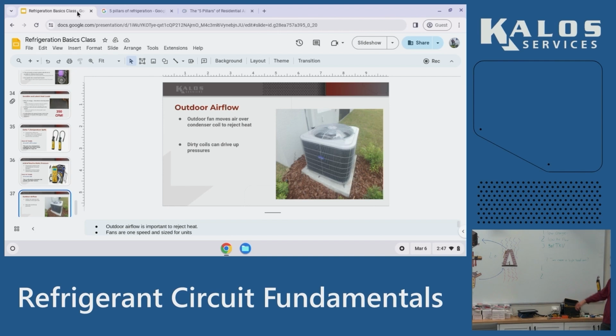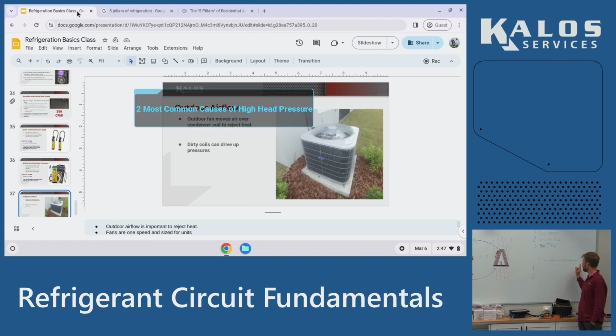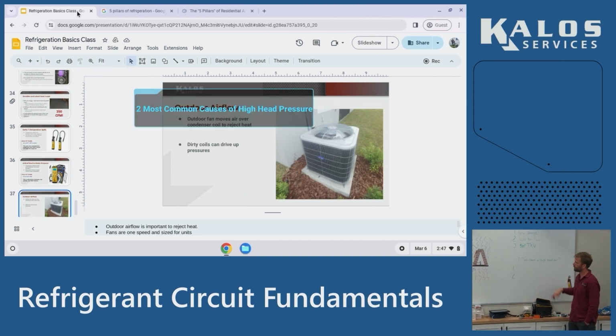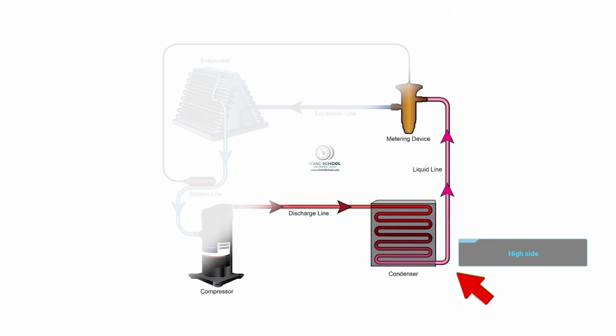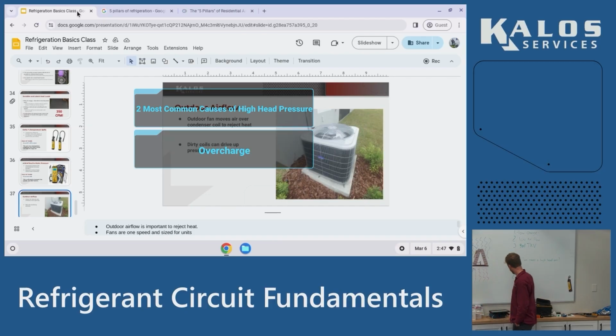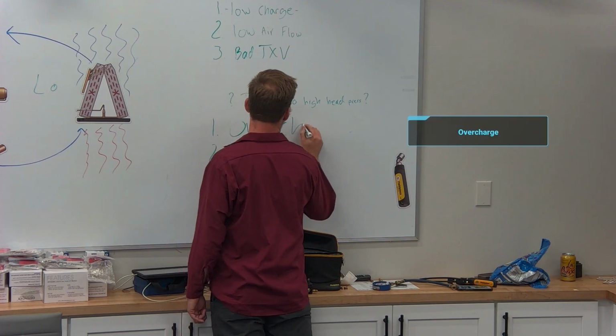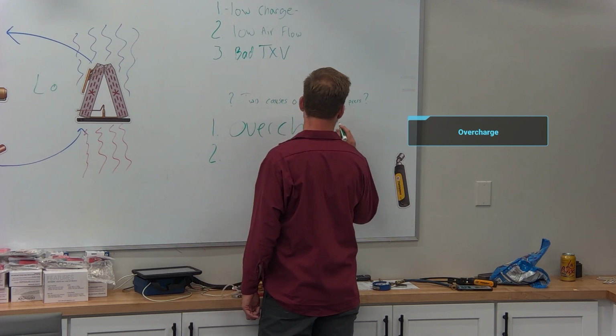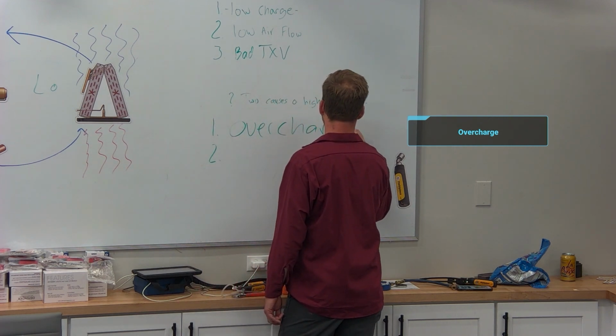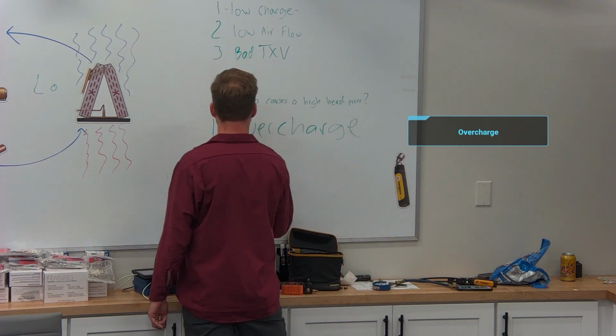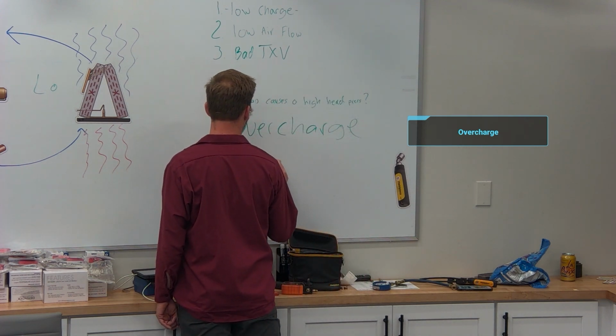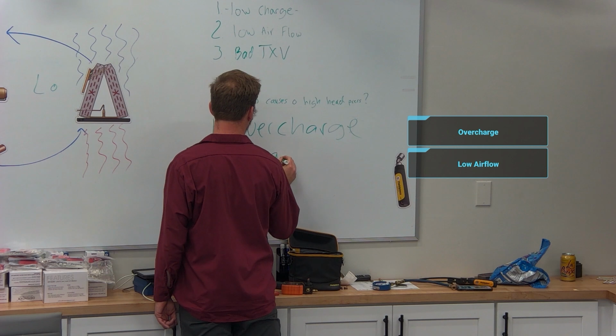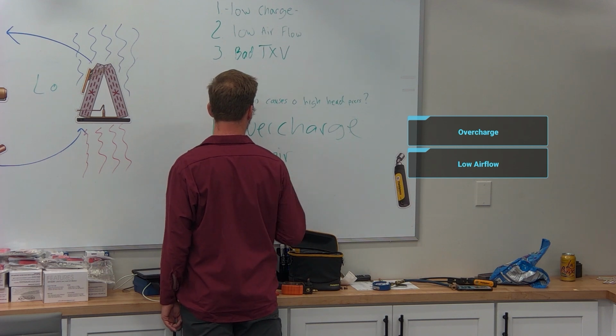Which brings us to the next one, two most common causes of high head pressure. Head pressure is our liquid pressure, is our condenser pressure, it's this whole side. Overcharge. I heard that. Because low airflow for that one too. Yes, it is. Which is the same thing. Both ways, yeah. Right? Dirty condenser, same thing as low airflow.